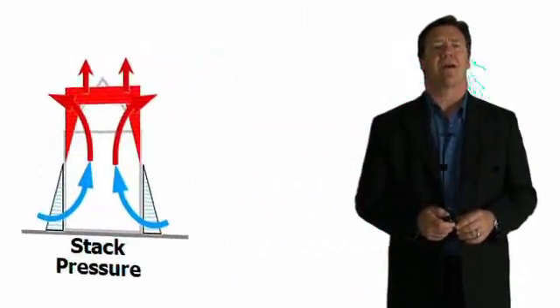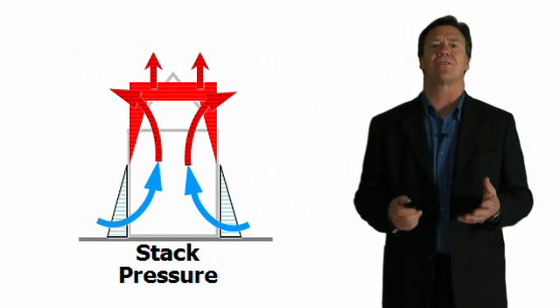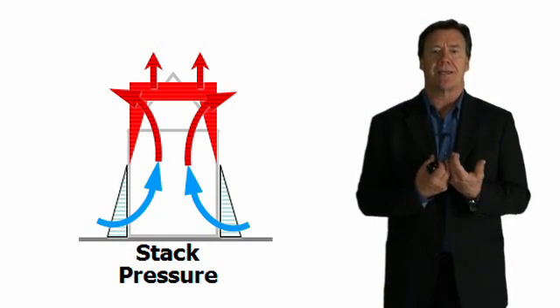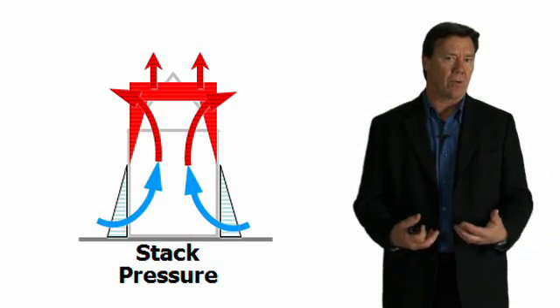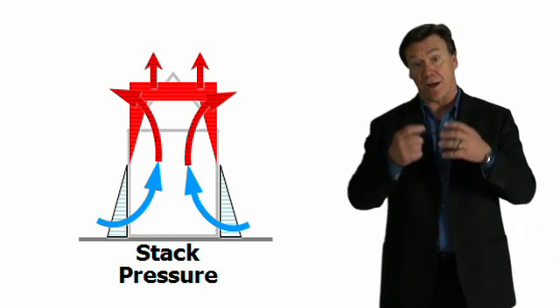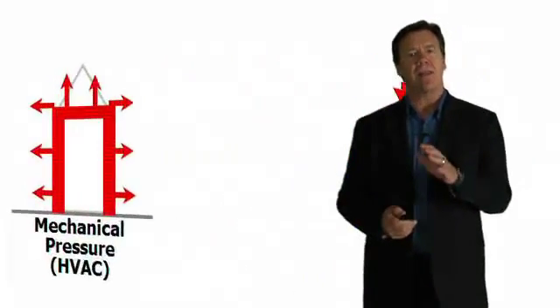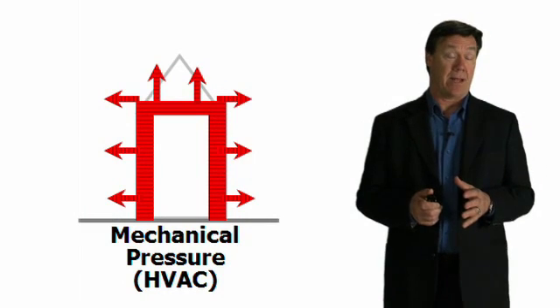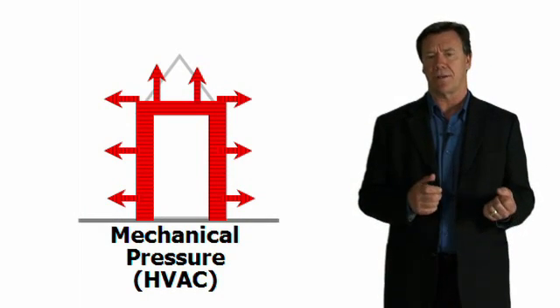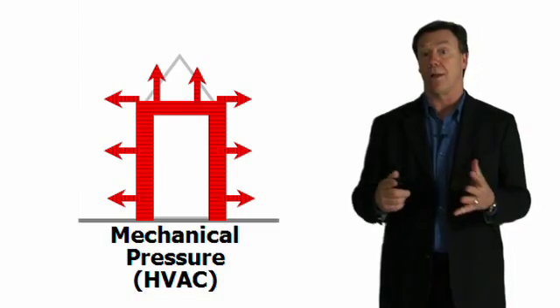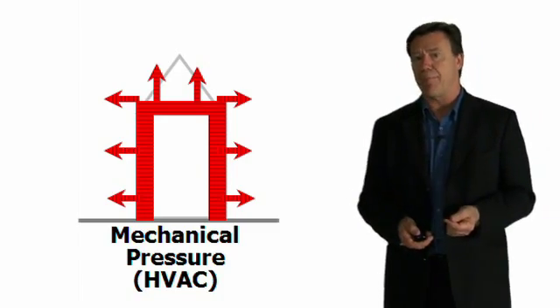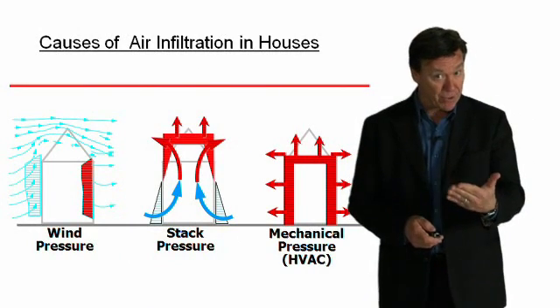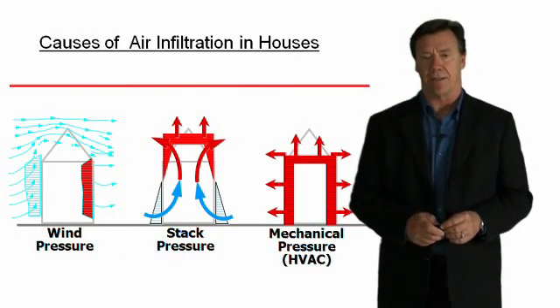The second cause is the stack effect. Warm air is more buoyant than cold air, so it wants to rise — we typically see air infiltrating into the lower parts of a structure and exfiltrating through the upper parts. Finally, mechanical systems: when HVAC equipment has duct leakage to the outdoors, it can cause the building to be under positive or negative pressure, with big impacts on overall building performance. That's why the code has a mandatory measure to seal ducts.